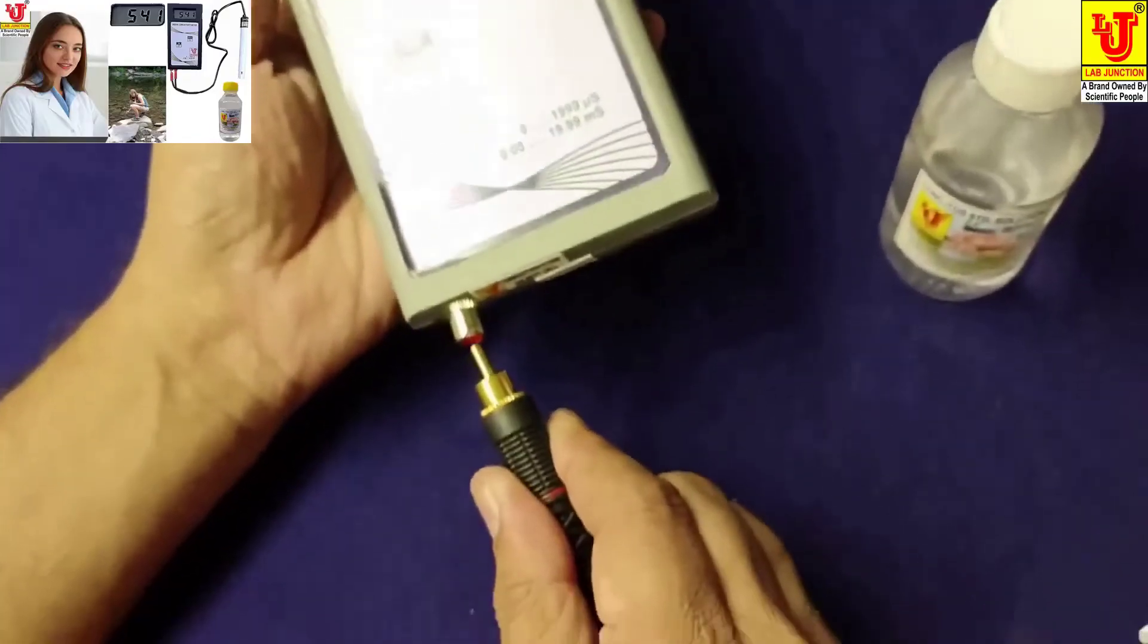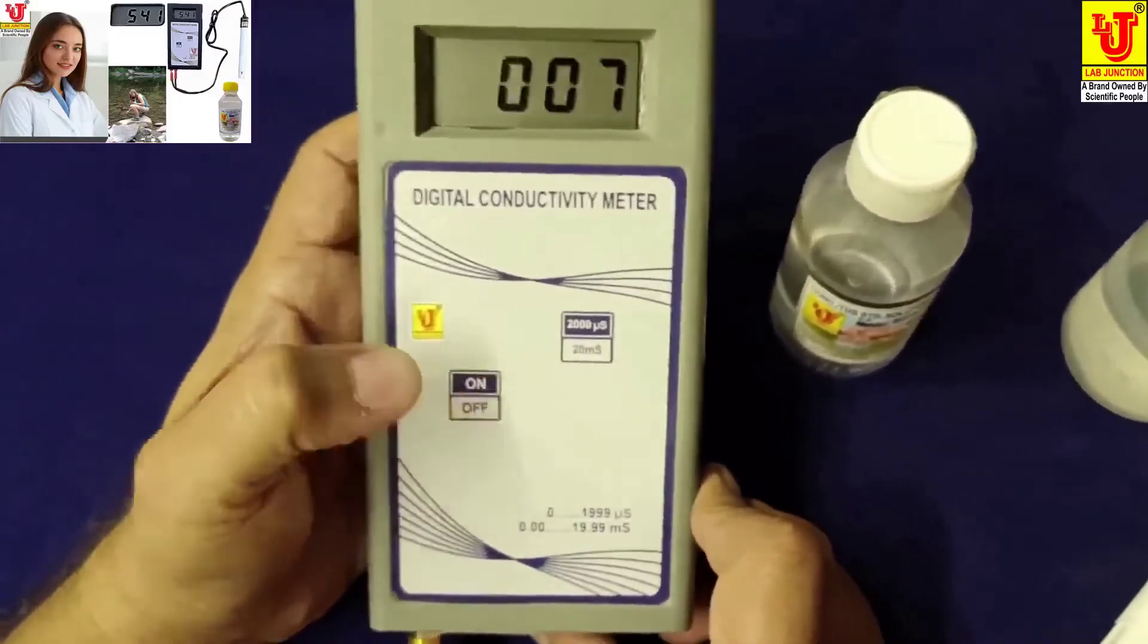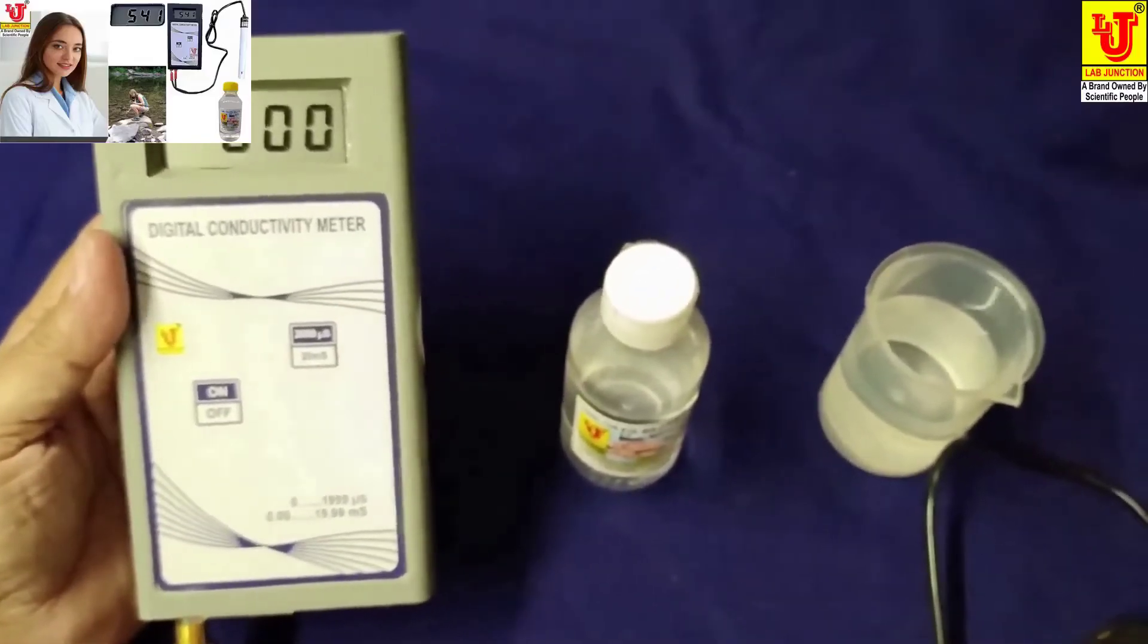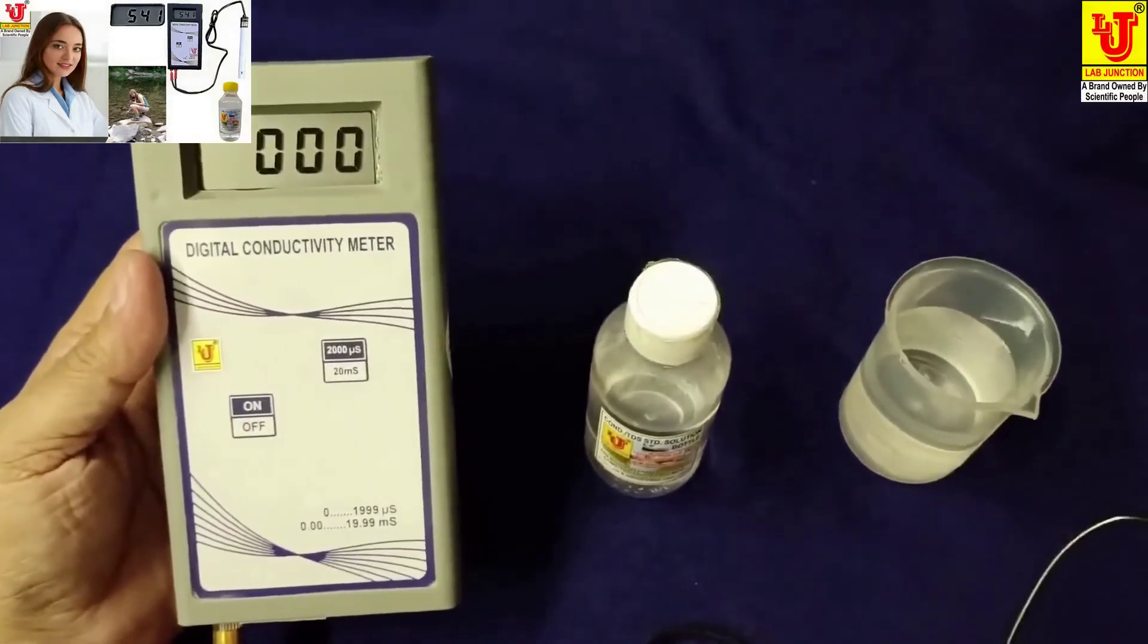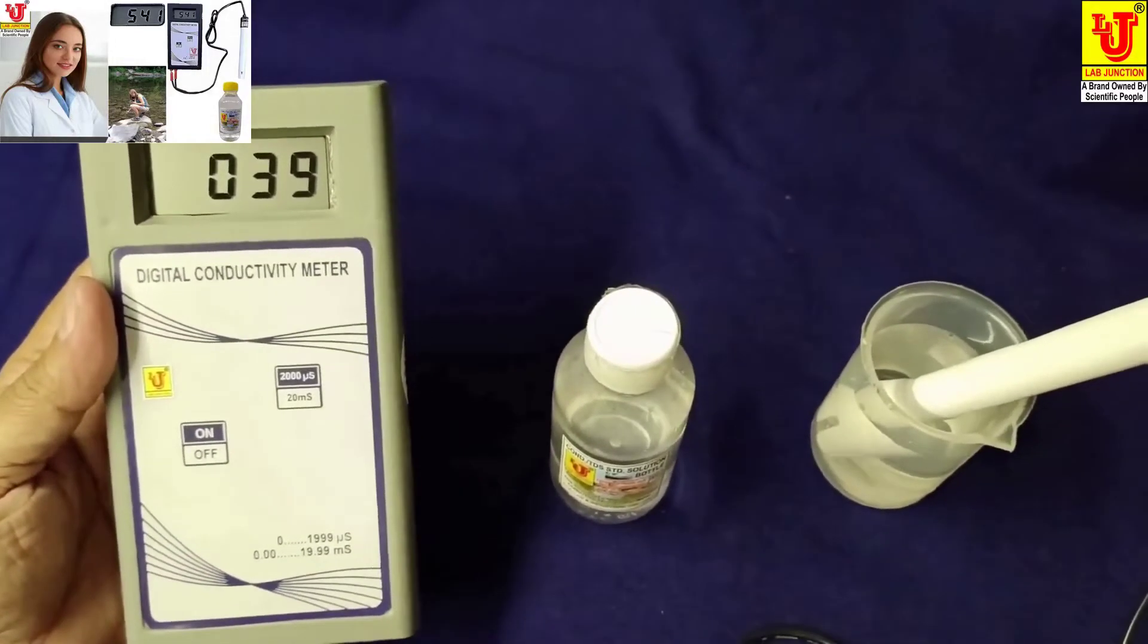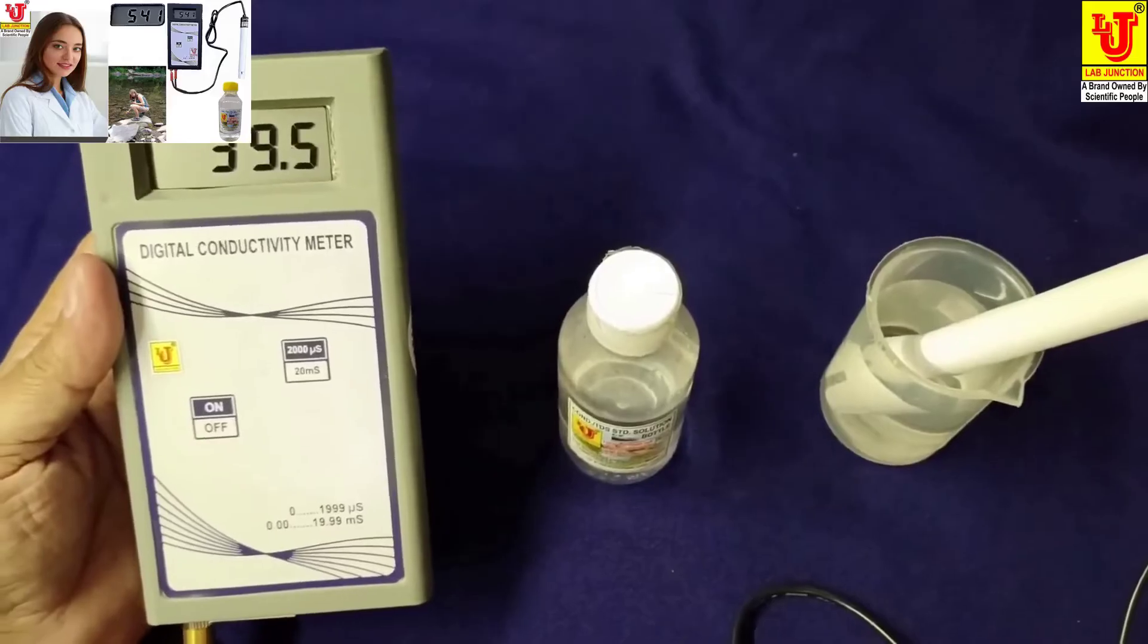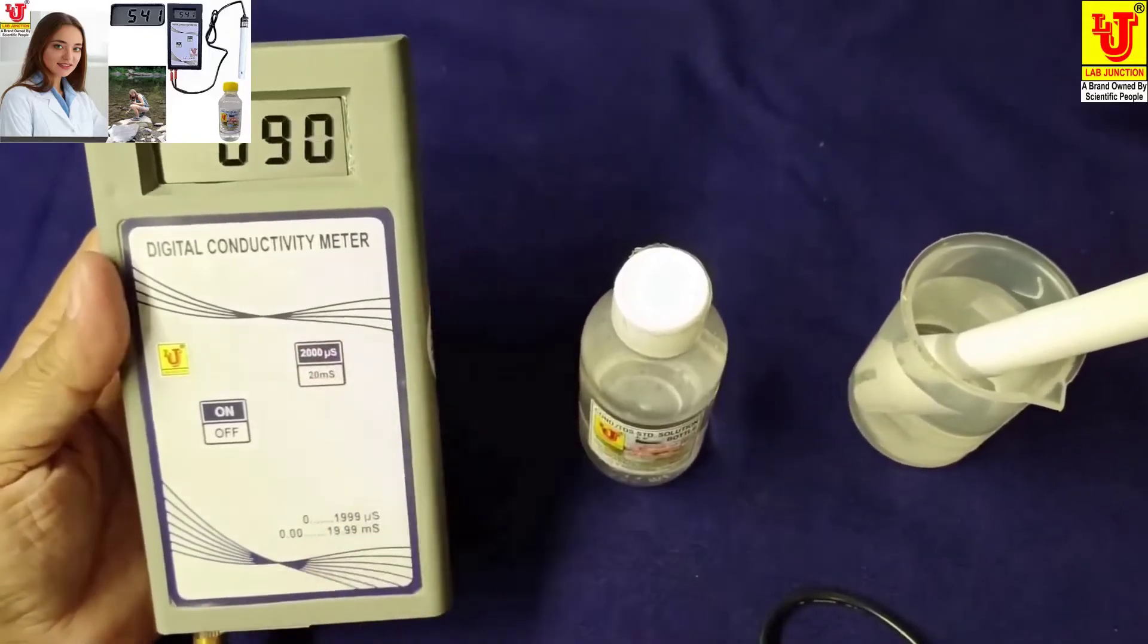Now first I am connecting conductivity cell with the instrument and switch on the instrument. Now suppose I am analyzing the test result from this instrument. Then directly switch on the instrument and dip your cell in the sample. This is 39 microsiemens and this is 0.039 millisiemens. This reading is in microsiemens and this reading is in millisiemens.